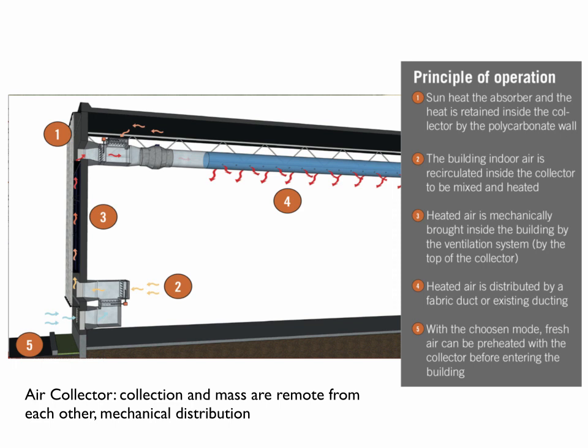Here's one where the air collector is on the south facade, and you can see that it's just hooked into the mechanical system. They're blowing air up in that cavity, and they can turn the air on, turn the air off. And because there's no glazing that's facing the interior, you're not losing any heat back out at night. So that's a bonus for it, and that's why it tends to be used more in cold climates.